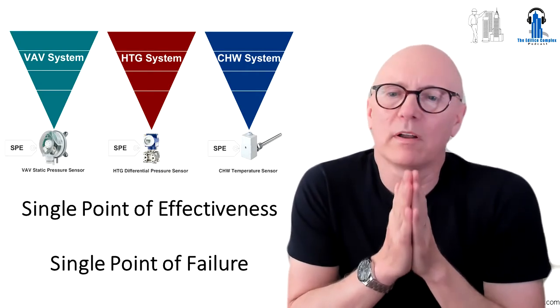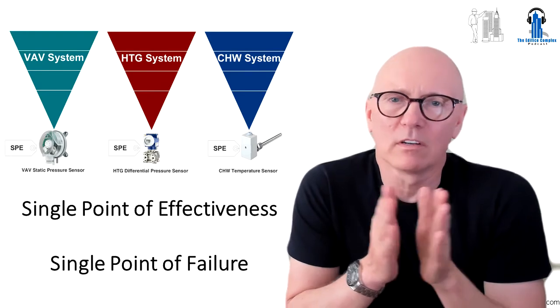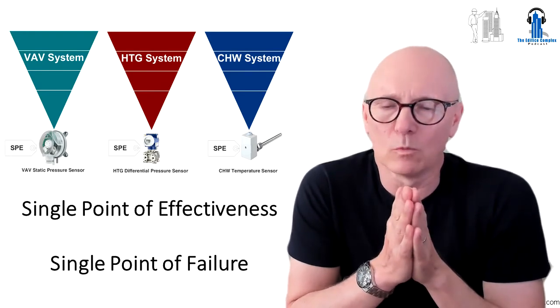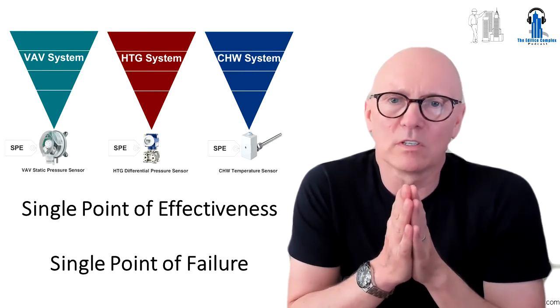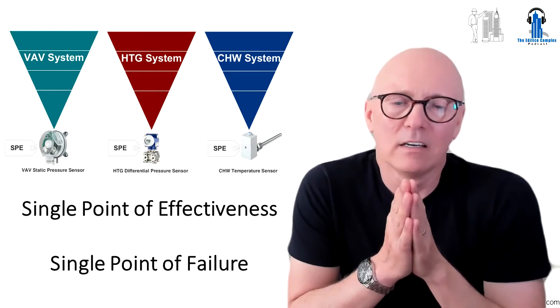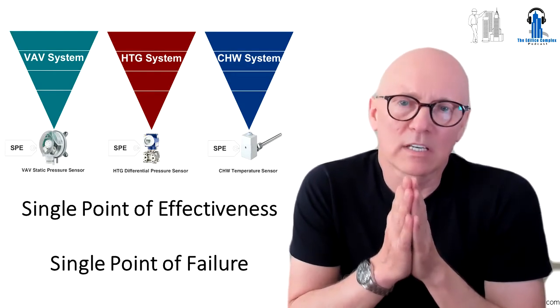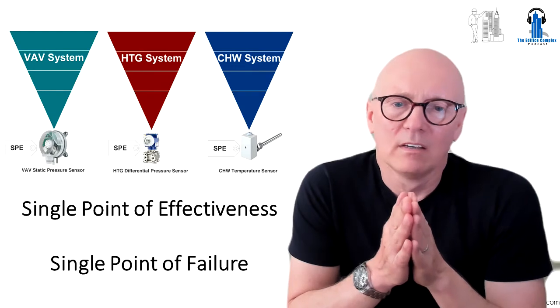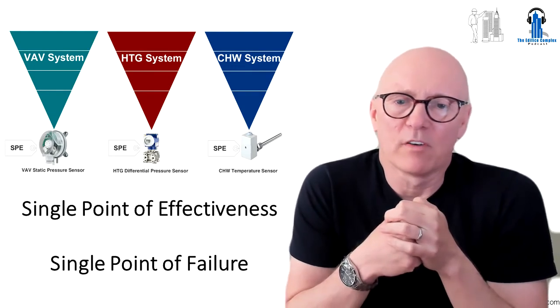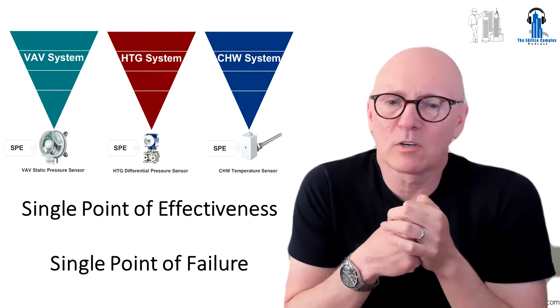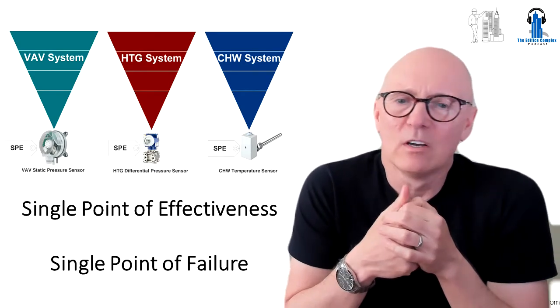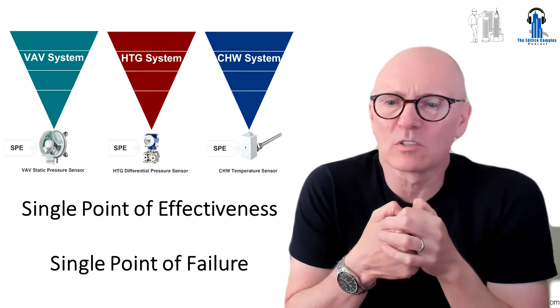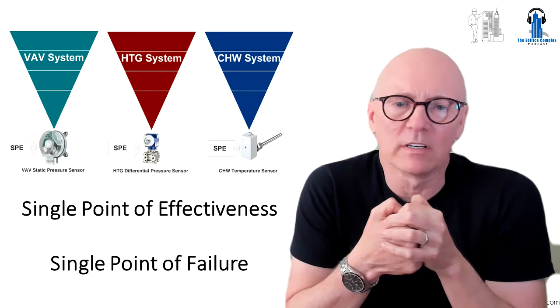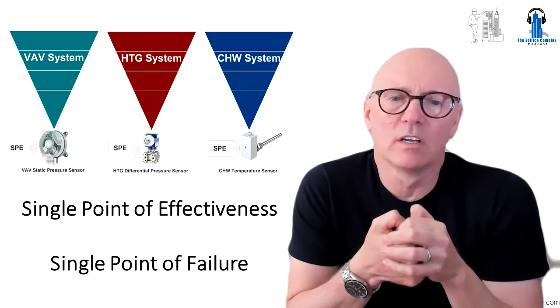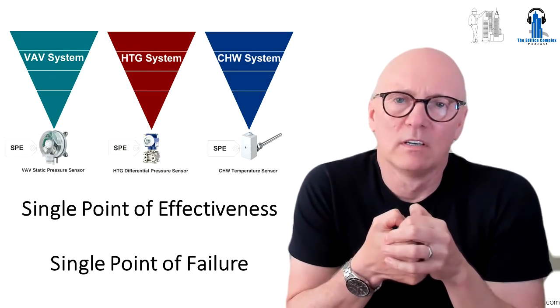There are no plug-and-play systems for large buildings. This is not like sticking a DX unit on the wall, split system on the wall. These buildings are complex and they need correct setting to work and commissioning. Also, most existing buildings have high energy costs, not because they need new chillers or they need new equipment, mostly because the key systems are not controlling optimally with empirically derived control system set points.